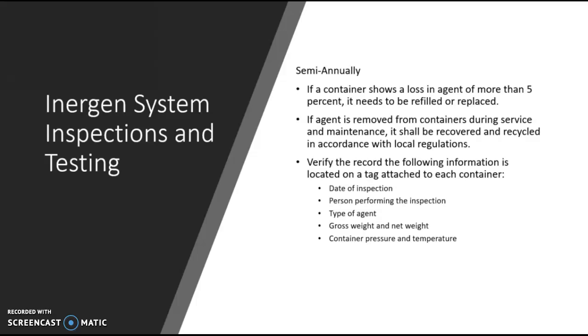Semi-annually, if a container shows a loss of agent of more than 5%, it needs to be refilled or replaced. If an agent is removed from containers during service maintenance, it needs to be recovered and recycled correctly per local codes. And local codes have that kind of stuff to them. And then verify a record of the following information is located on the tag attached to each container. We want to make sure the date of the inspection, person performing the inspection, type of agent, gross weight, net weight, and container pressure and temperature are located on each container.